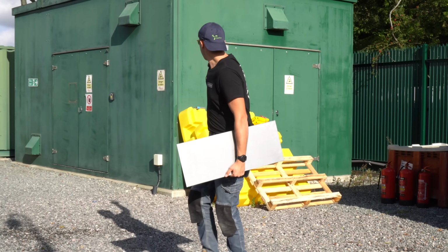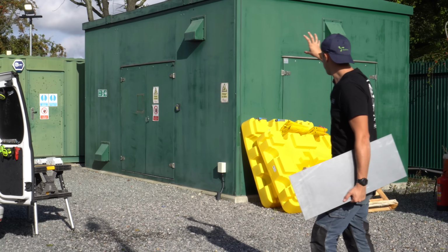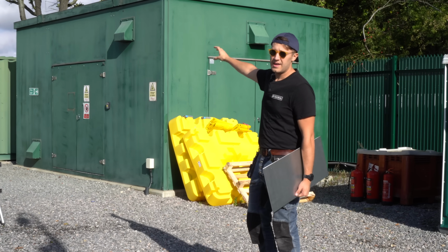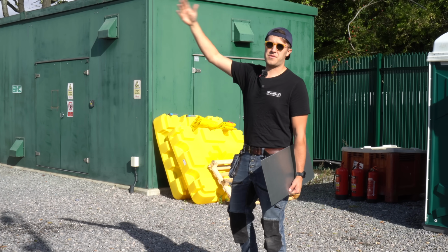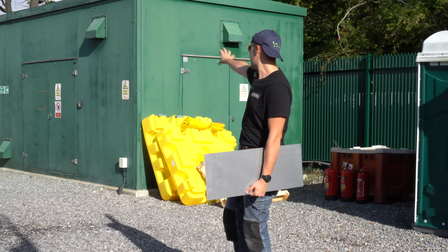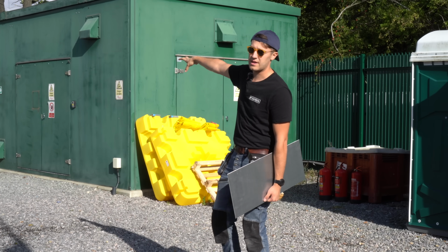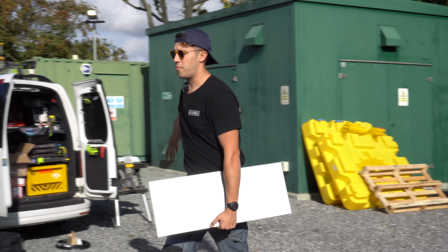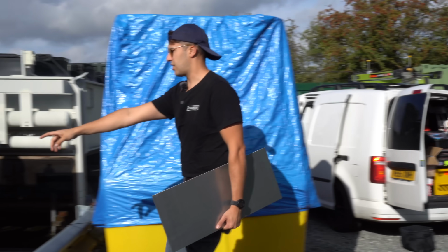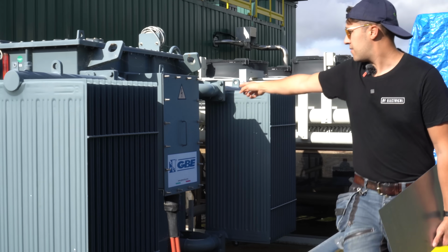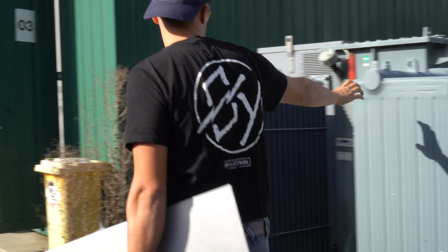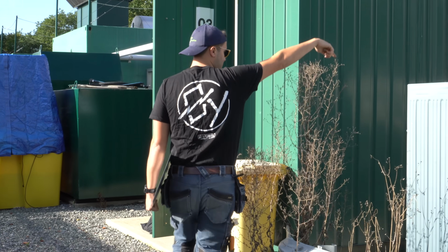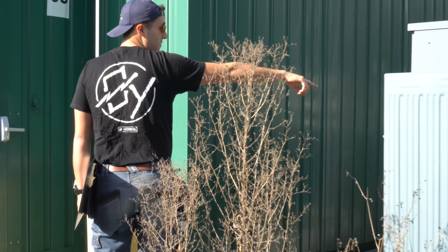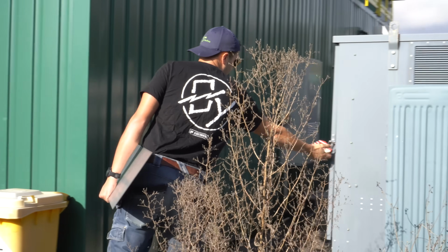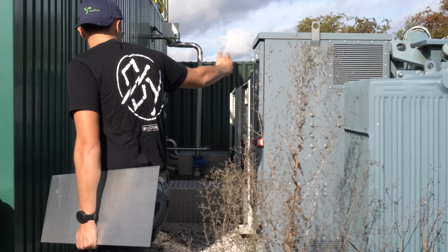So this here is the HV, this is where the power comes into the property. High voltage in the UK is anything over 1,000 volts. Typically inside there you'll have either 11 kV or 33 kV. That comes through a breaker up to this transformer here. That HV is still live, but we're not touching that side of it. It's then stepped down to LV, which in this instance would be 415 volts. It's safely isolated and then off a breaker in there, up into the panel in question.